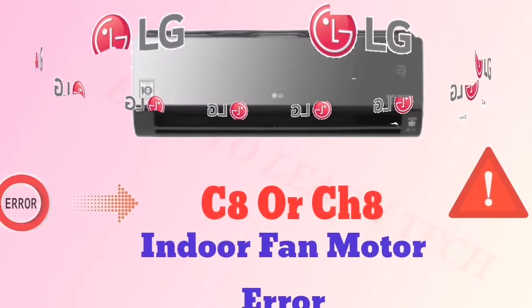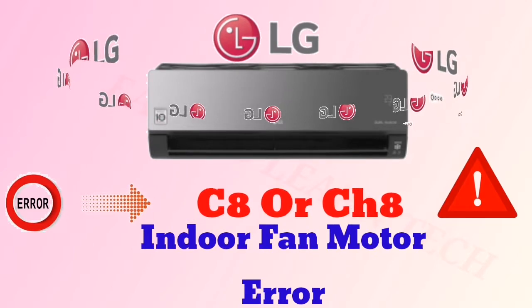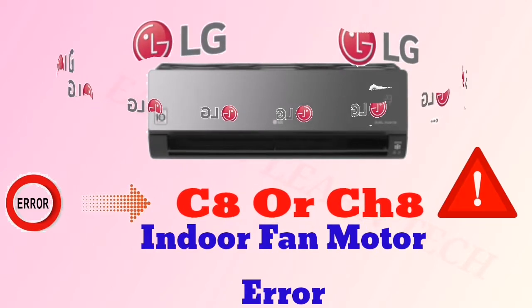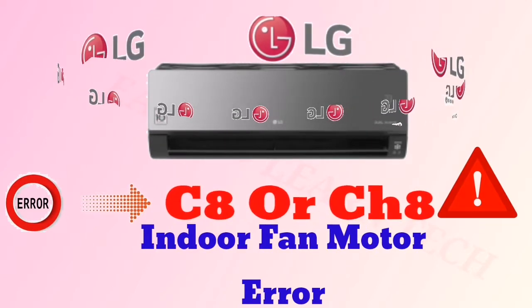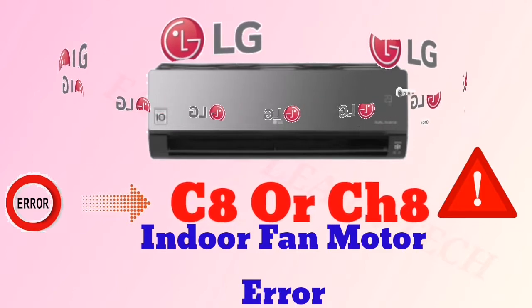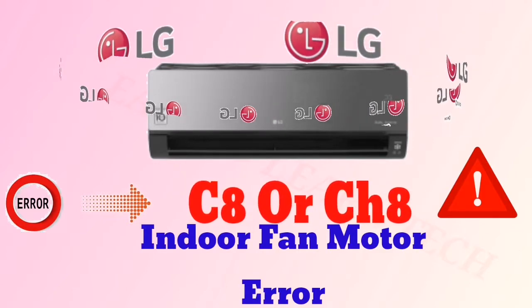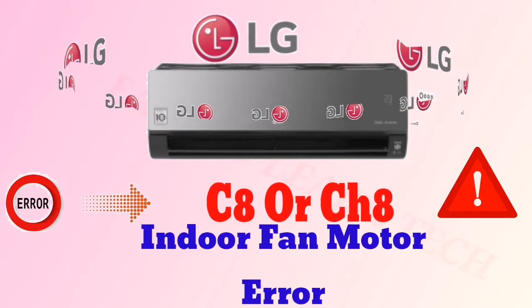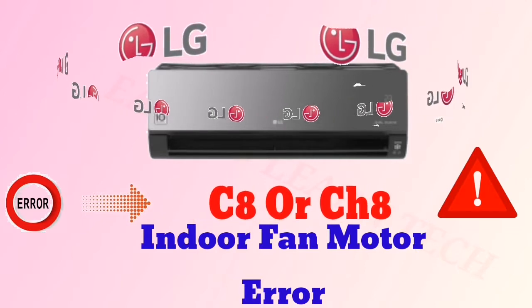Let's see the next error code. When you see C8 or CH8, it means indoor fan motor error. First of all, you have to rotate your blower with your hand to check if your blower is stuck somewhere or not. If it is not stuck, then you have to follow the next process. Then you have to check the output supply of your indoor PCB.